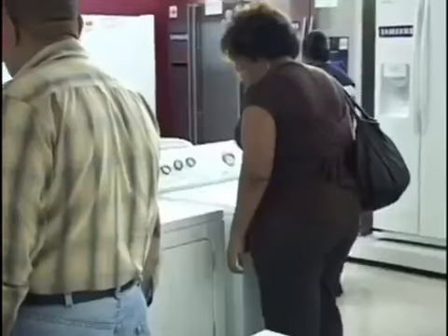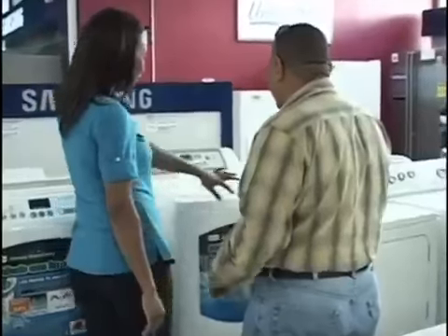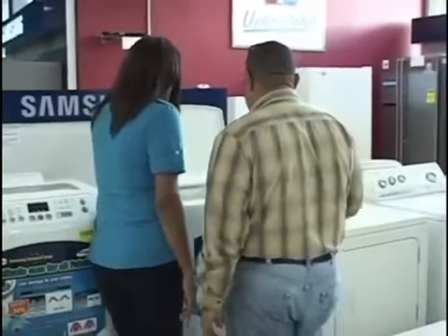If that explanation was a bit too much to absorb, then all you need to remember about electricity cycle is this. For example, if you were to buy a 60 cycle piece of equipment in the States and bring it to Jamaica, where we have 50 Hertz, that piece of equipment would draw more current than it was designed for. That can lead to inherent problems. It will lower efficiencies, and it could cause the motor to burn in instances, because now you're drawing more current than the equipment was designed for.